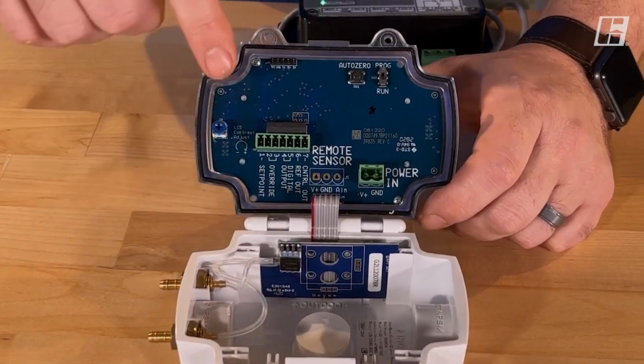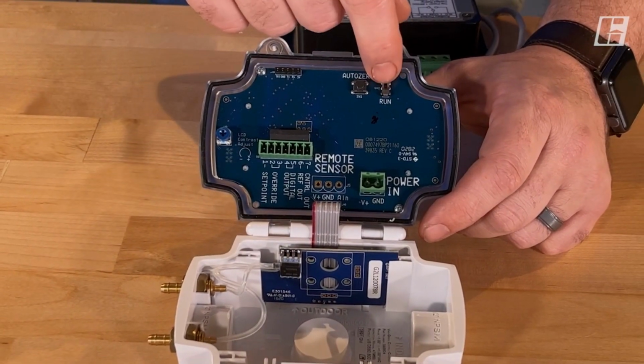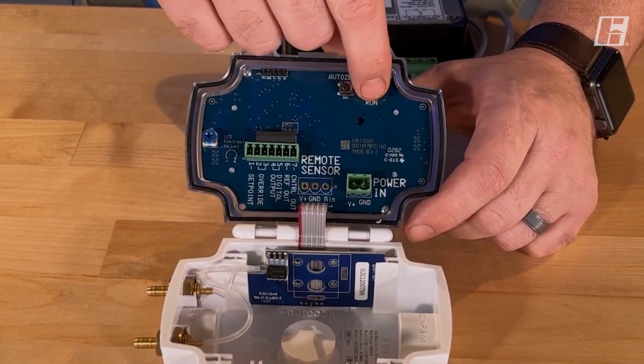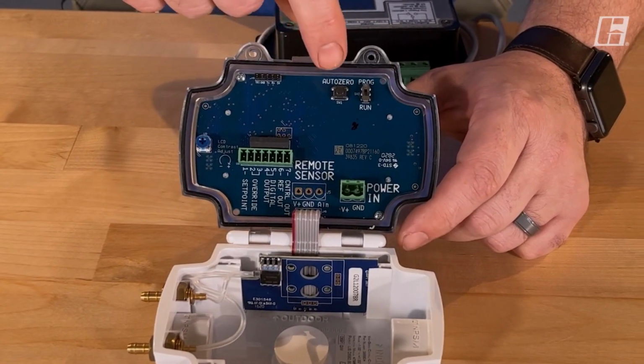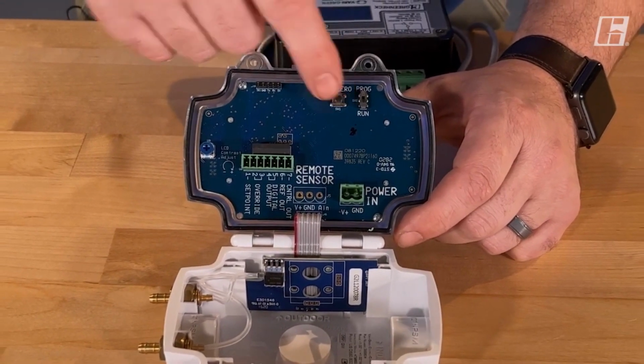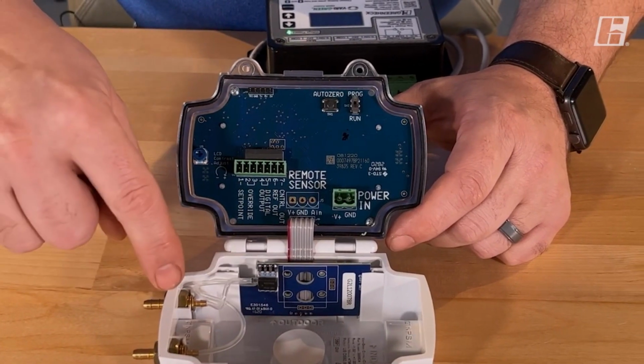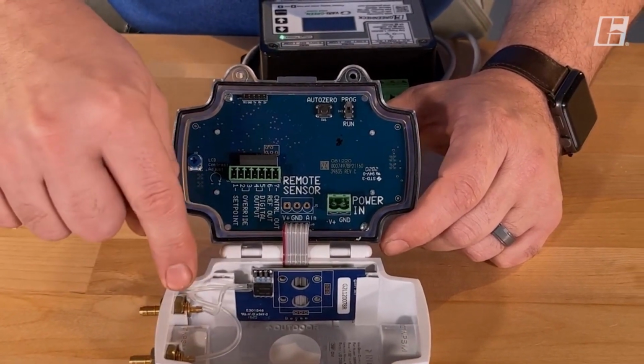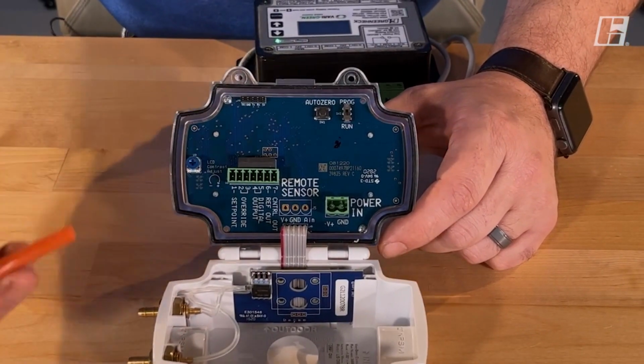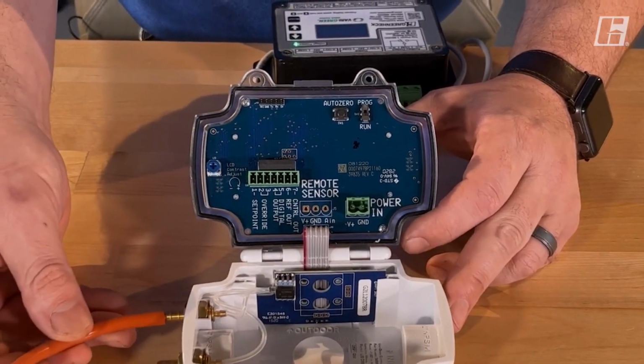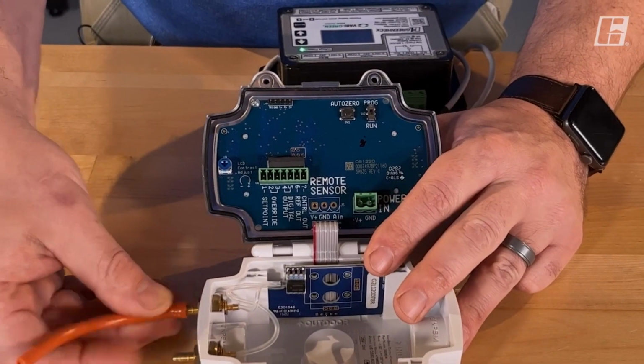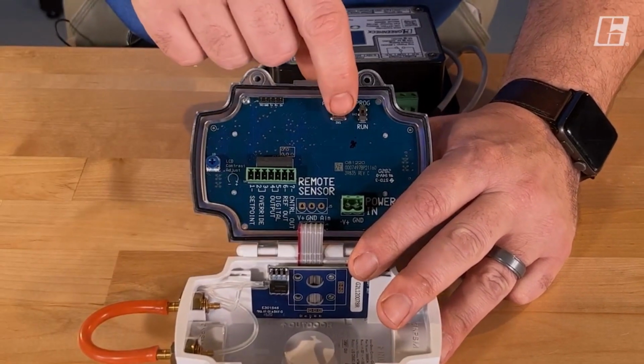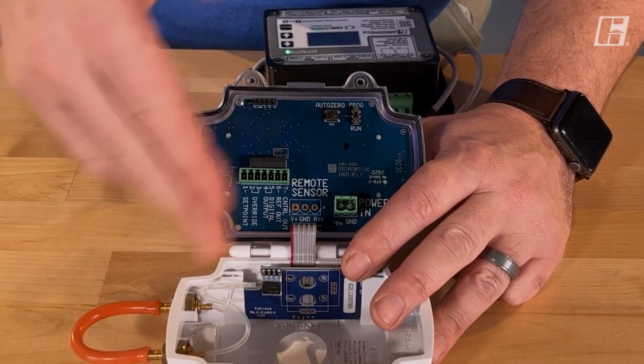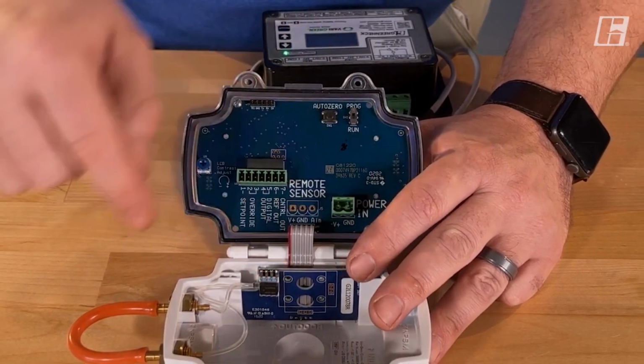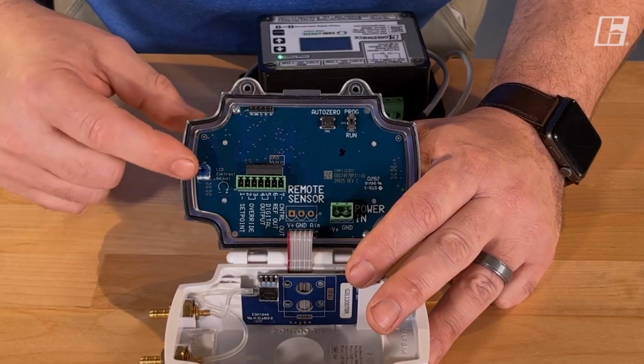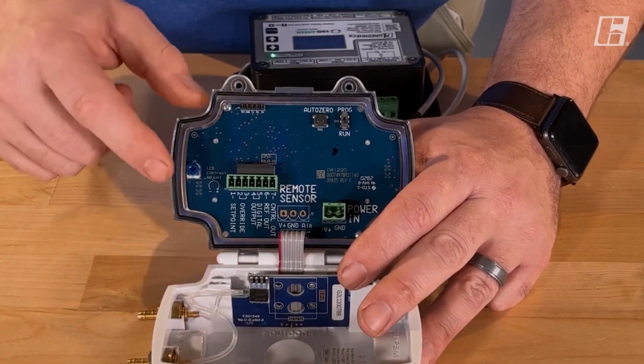There's a couple of things that we can point out also in here. We have a toggle switch to allow us to go from run mode to program mode. There's an auto 0 button. The auto 0 button allows the pressure transducer to zero out between these 2 ports. Typically what you'll do is take a short section of tubing, put it on the ports, and then go ahead and depress that auto 0 button. So there's 0 pressure difference between the 2. Now we are calibrated. Other buttons in here, we have a contrast potentiometer for the screen.